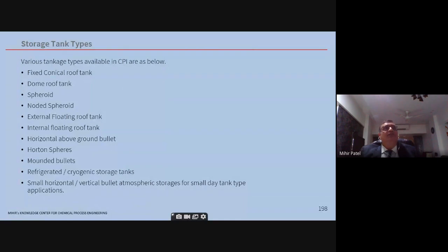First is the fixed conical roof tank. This is always used for water services or for high boiling chemicals. Like if you have a fuel oil tank, you can have an open gooseneck vent at the top, and since it is to be stored at, let's say, 100 degrees centigrade, you don't have flammability at the top, so you can keep an open gooseneck and you can keep a fixed conical roof tank.